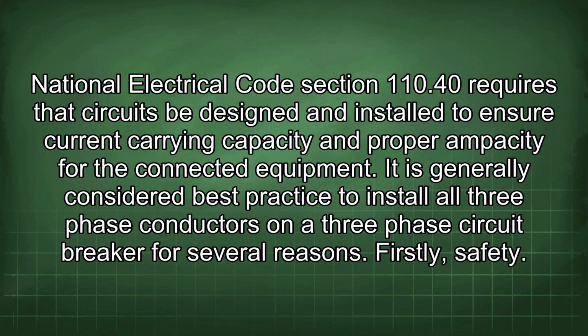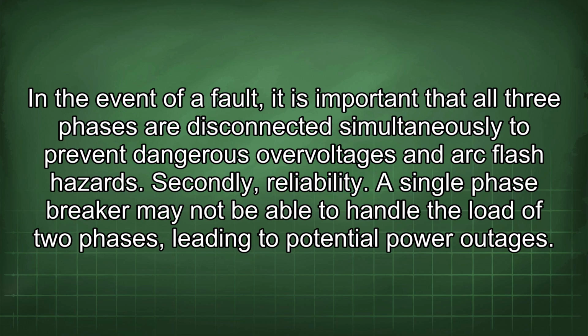It is generally considered best practice to install all three-phase conductors on a three-phase circuit breaker for several reasons. Firstly, safety: in the event of a fault, it is important that all three phases are disconnected simultaneously to prevent dangerous overvoltages and arc flash hazards. Secondly, reliability: a single-phase breaker may not be able to handle the load of two phases, leading to potential power outages.